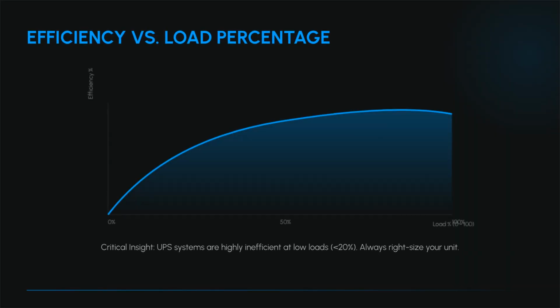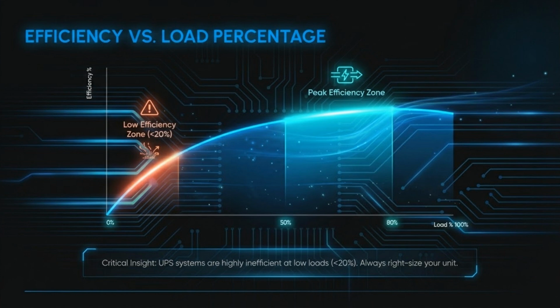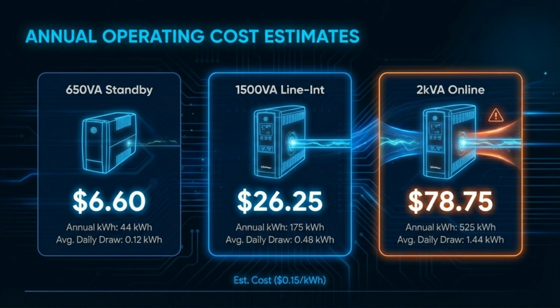When examining efficiency versus load percentage, a critical insight is that UPS systems are highly inefficient at low loads, specifically below 20%. To maximize efficiency and minimize waste, you should always right-size your UPS unit to avoid the low efficiency zone. Annual operating cost estimates show the difference based on unit rating. A 650 VA standby unit costs about $6.60 annually, while a 2 kVA online unit costs around $78.75, assuming 15 cents per kilowatt-hour. The continuous power draw dramatically increases the estimated annual energy cost for higher capacity and less efficient UPS topologies.